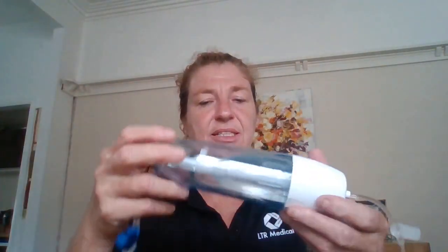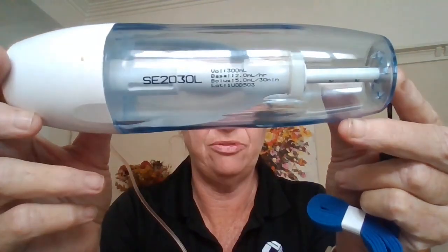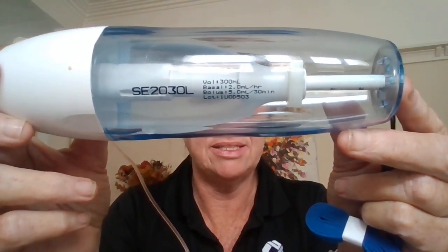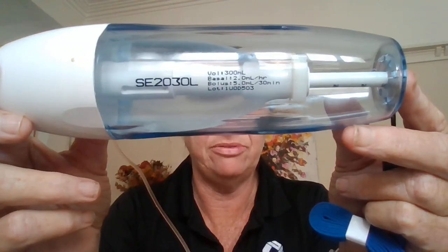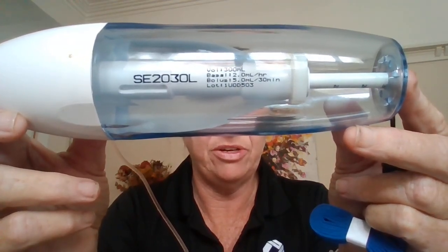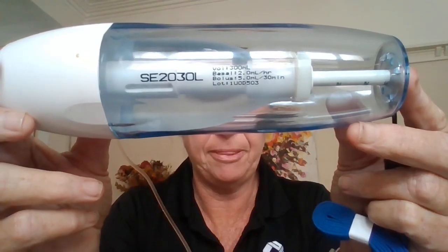Once you do open the canister, you can see I have already partially filled this, and once again the details that are on the outer package are also on the device itself. So you can see that once again there. It has the volume of 300 mils, a basal rate of 2 mils, a bolus of 5 mils with a 30-minute lockout. It also has the lot number attached. Now the Accufuser does not need to be filled completely, but it does need to be filled at least to 50%. So with this being a 300 mil size, you must put in 150 mils, but anywhere from 150 mils to 300 mils is suitable.